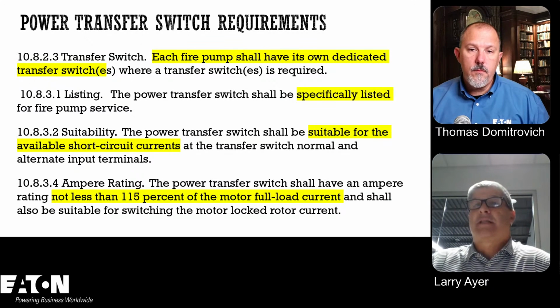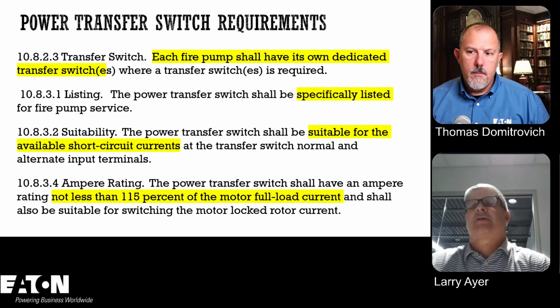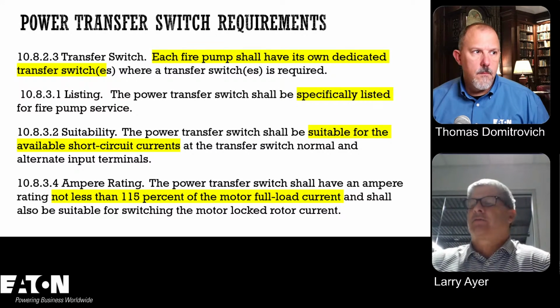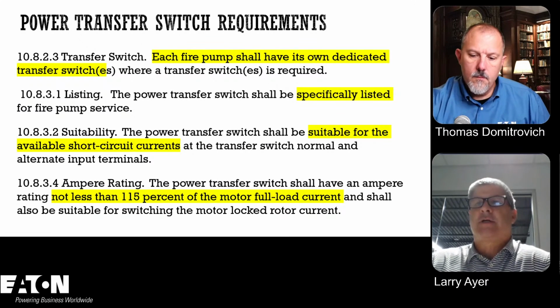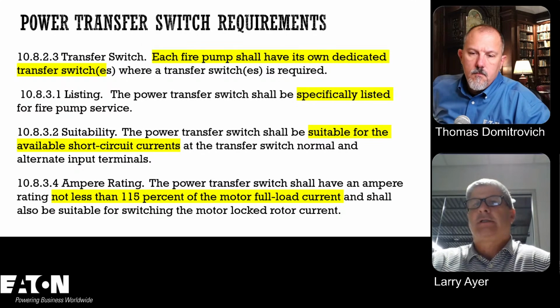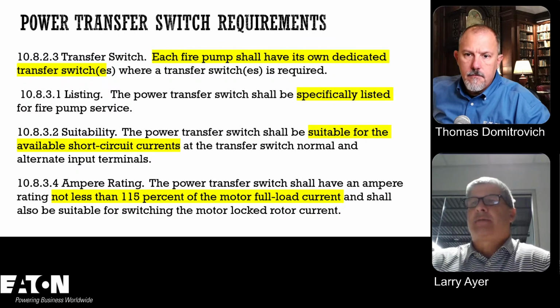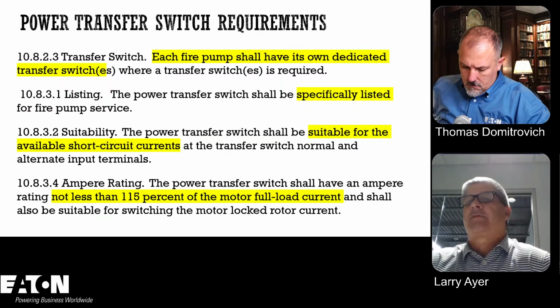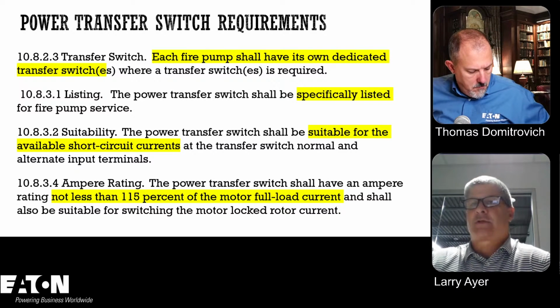Right. So these transfer switches have to be listed. Yep. They have to be dedicated to that fire pump. You can't put other loads on there. They also have to be suitable, and this is the whole theme throughout the NEC. It's not just for fire pump transfer switches. It goes for transfer switches, overcurrent devices, receptacles, everything. Each device that you install in an electrical system has to be suitable for the available short circuit current. A receptacle has a short circuit current rating of 2,000 amps. Not many people know that, but each device has a rating, and so we have to do that for transfer switches as well, and fire pump transfer switches.